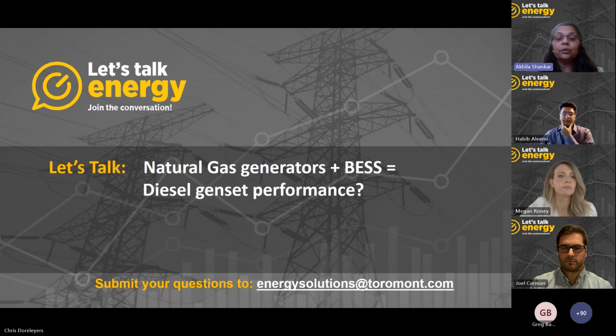Please do check out our videos that are on YouTube. You'll be able to see a 2.5 megawatt natural gas fast response genset starting in under 10 seconds and taking 100% block load in one step. You will be impressed. While it is impressive that a natural gas genset does not stall at 100% block load, you will see, however, significant dips in the genset voltage and frequency. But when a battery energy storage system is used with the natural gas gensets, it does support the transient block load and the motor starting requirements, thereby reducing the magnitude of the voltage and frequency dips, and it also improves the recovery time to the rated values.